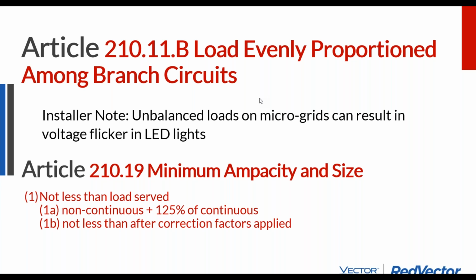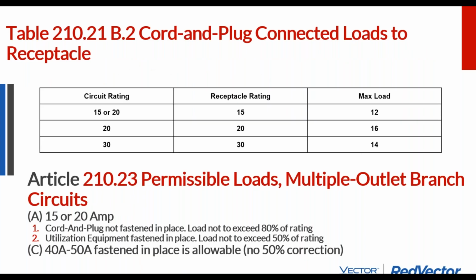which once you get into solar, well, solar is on for 3 hours or more, and it's a continuous load, so you need to upsize by 25%. But then beyond that, you get into different performances at cold temperatures versus hot temperatures, and that allows for additional ampacity allowances of another 25% under certain uncontrolled natural cases.